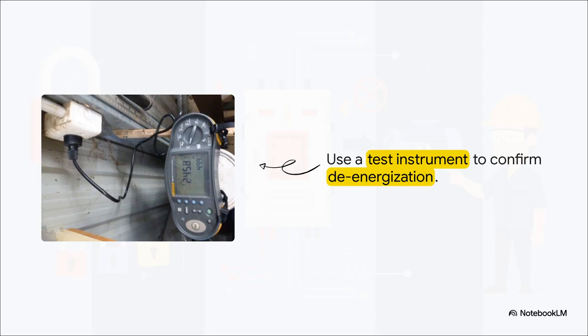The golden rule: all conductors must be treated as live until proven dead. You can never just assume a flipped breaker actually worked. Plus, please do not rely on a proximity tester as your primary tool, because they literally do not detect DC voltage. You need a properly rated contact test instrument, like a high-quality multimeter that's fully capable of withstanding fault currents.